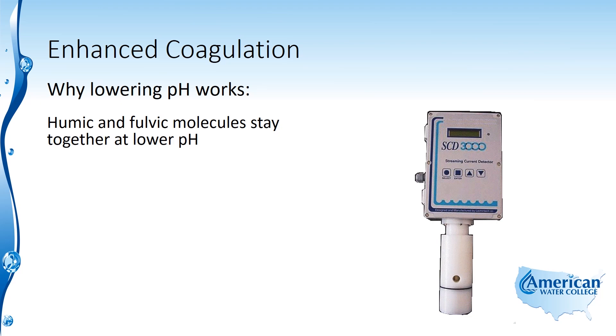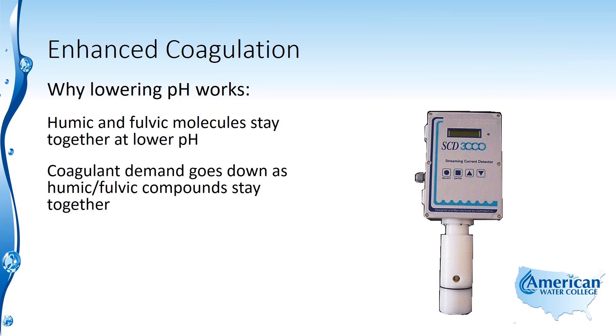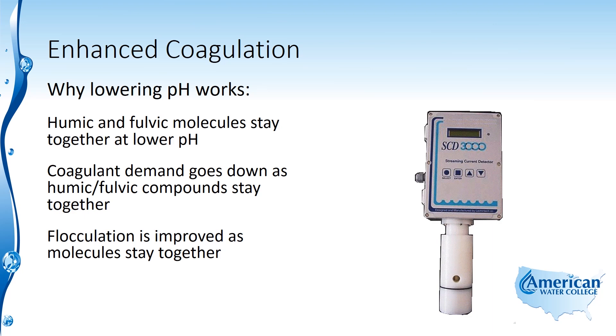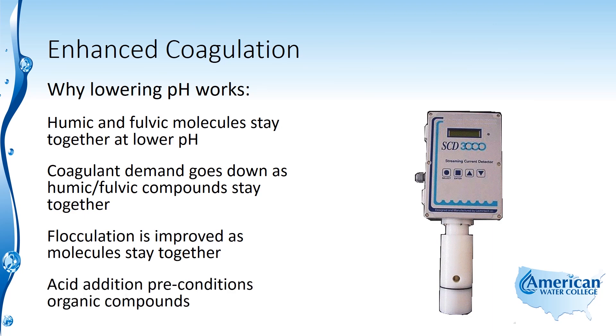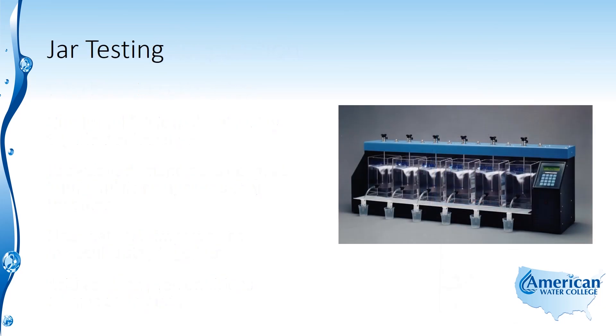Why does this work? Humic and fulvic molecules stay together at a lower pH. These humic and fulvic molecules are the natural organic or decaying organic material found in surface water supplies. At a lower pH, they tend to stay together, which helps with the flocculation. The coagulant demand goes down as these compounds stay together, and flocculation is improved. The acid addition — because that's how we lower the pH, typically by adding sulfuric acid — preconditions the organic compounds and helps the flocculation process.